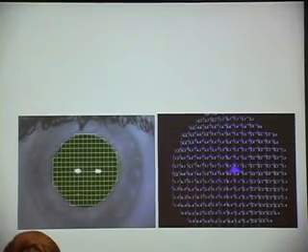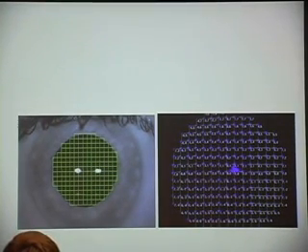If you have a really highly aberrated eye, you'll see some strange patterns. The spots will be squished in one axis and elongated in the other, or you can have almost anything going on. To do this properly, you have to know which hole, or which lens, corresponds to each spot. So this is an interesting image analysis problem. You end up creating a graph that compares adjacent spots and builds up a web which you think is the most likely characterization.